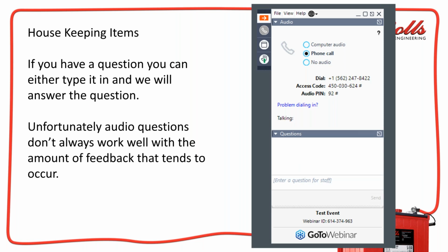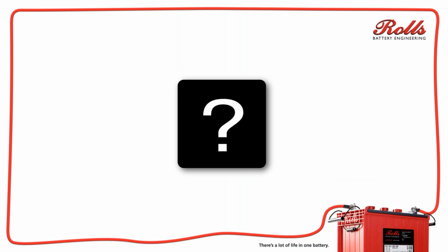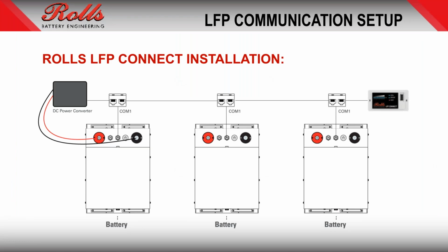All right, so the question I got this morning from a customer was addressing trying to recover a battery bank, a discharged or even an abused battery bank. With discharged or abused battery banks, it can take time to recover them. Just to give an idea, from a 1.220 specific gravity, it can take 6 to 8 weeks of daily charging to get those batteries to recover.